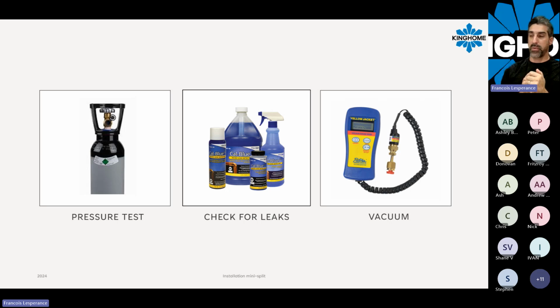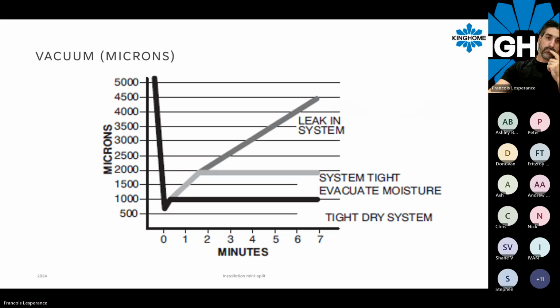That's the most important part. Make sure you remove all the air and humidity inside the system. To make a right measurement, you will use a micron gauge. The micron gauge is the one that will tell you if you have a leak in your system or if you still have humidity in your system.